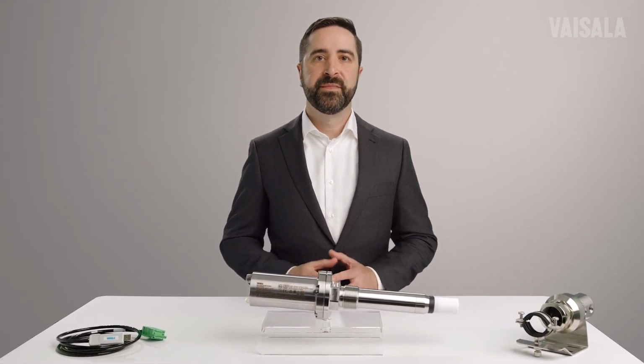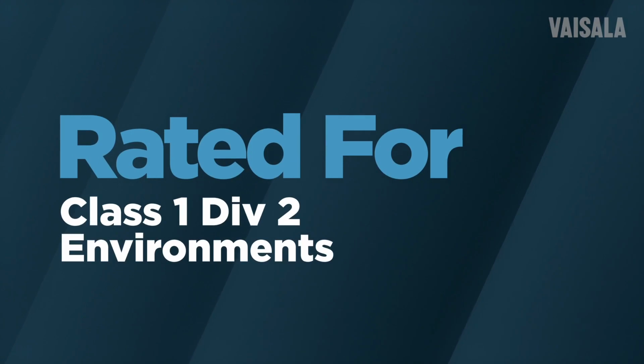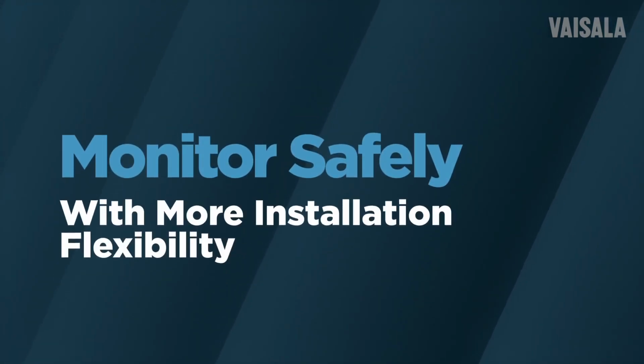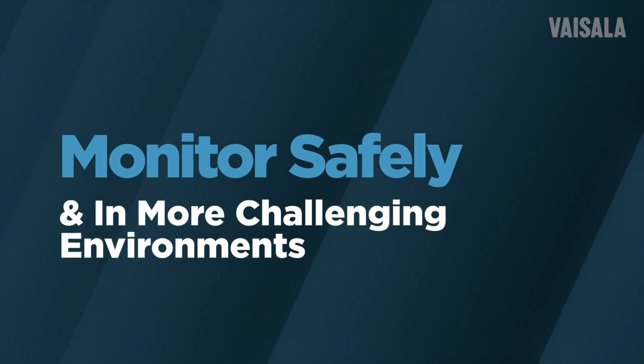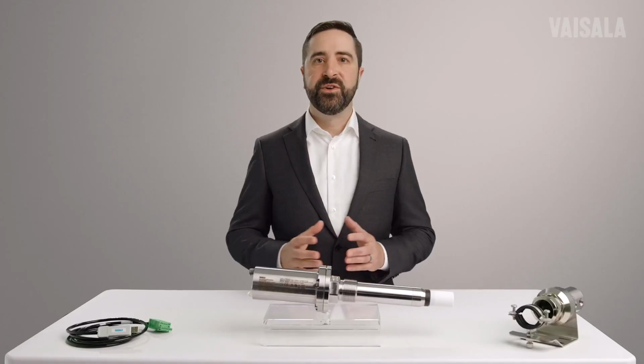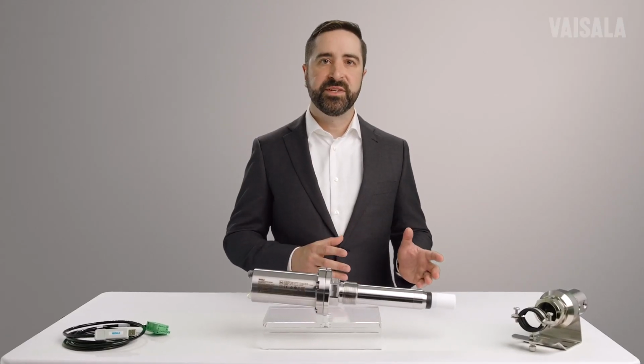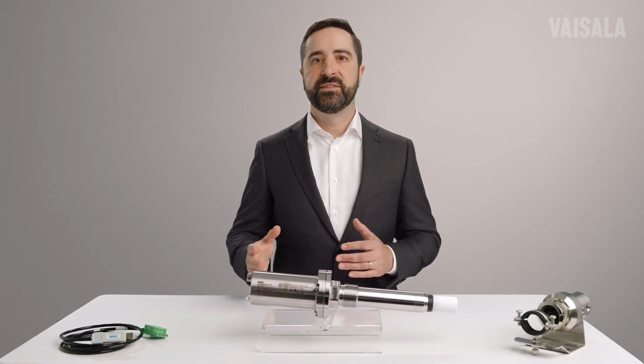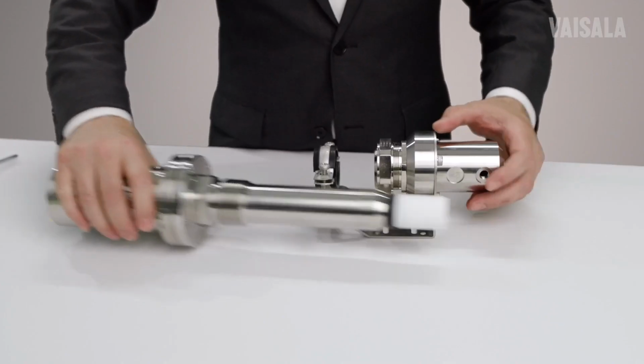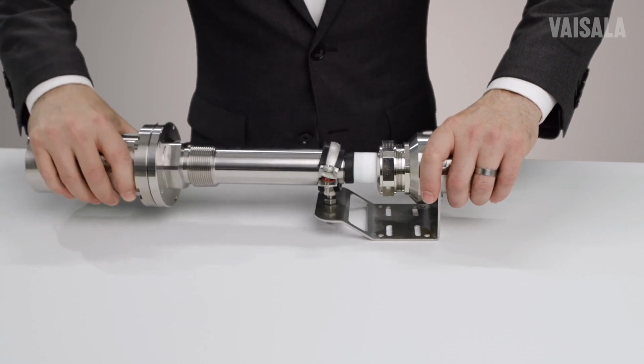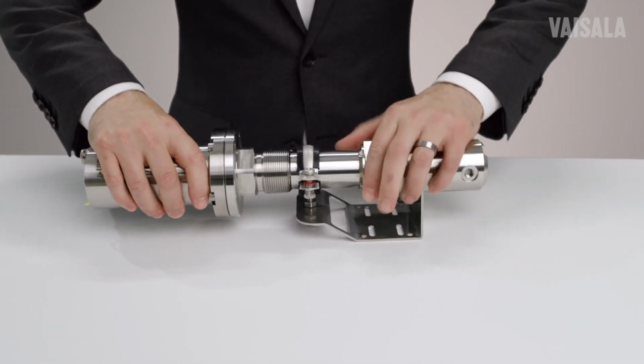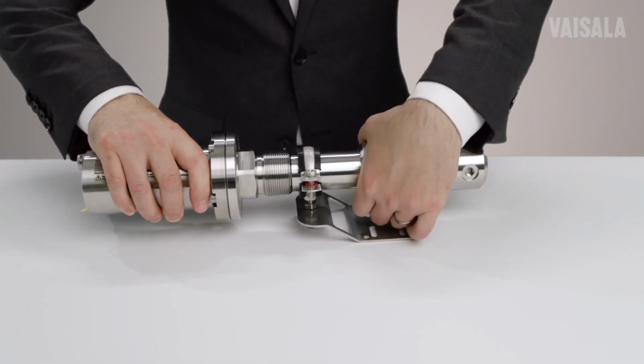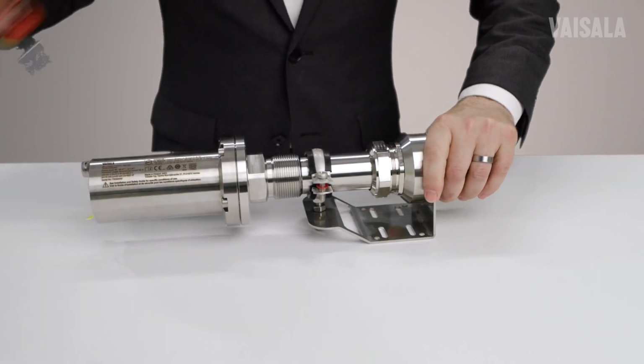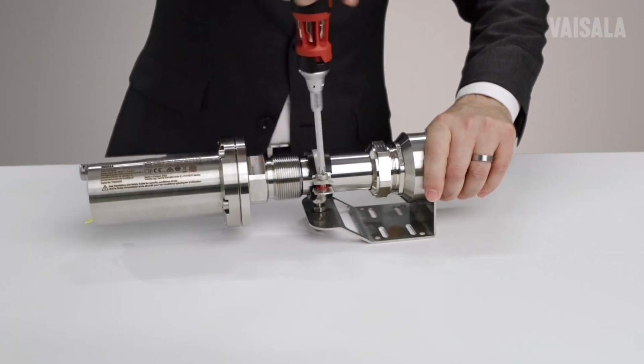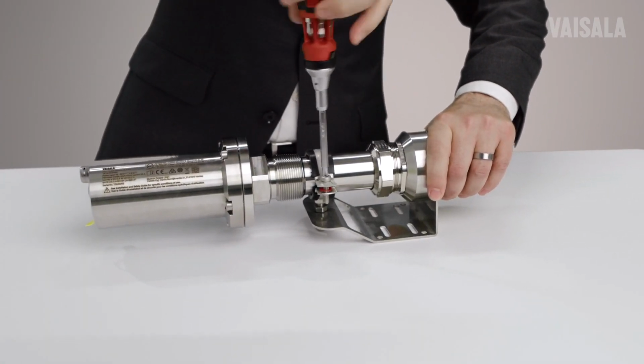Rated for Class 1 Div 2 environments, the MGP260 series probes monitor safely with more installation flexibility in more challenging environments. There is no need for an additional structure to bring a sample to, or heat tracing to consume electricity. The common 1.5-inch NPT threaded interface allows for direct installation or through a 2-inch ball valve, and the optional flow-through accessory allows for a wider variety of installation options.